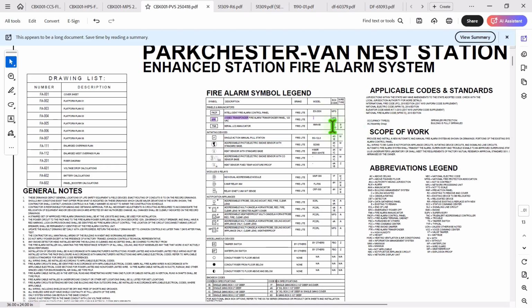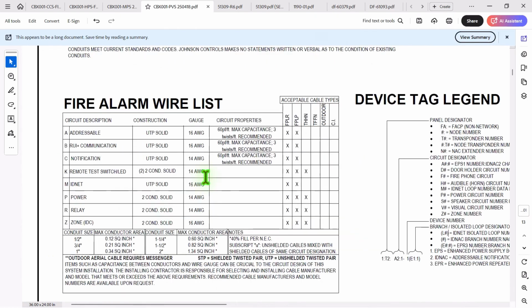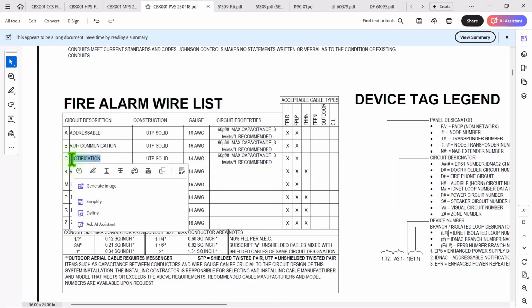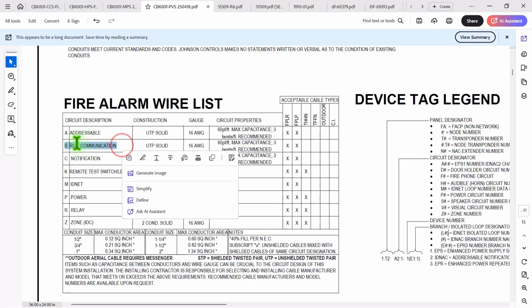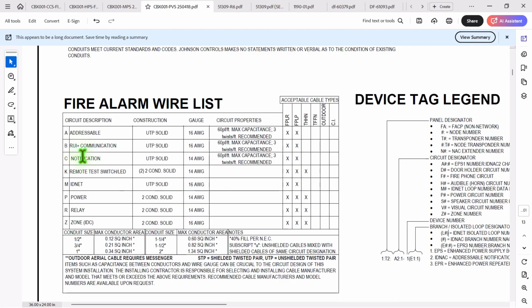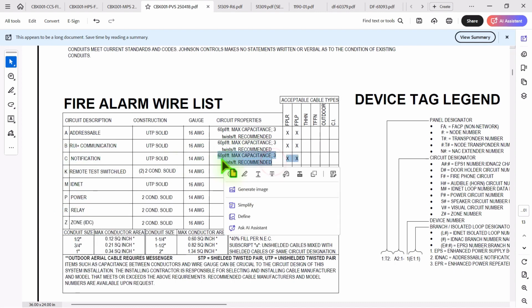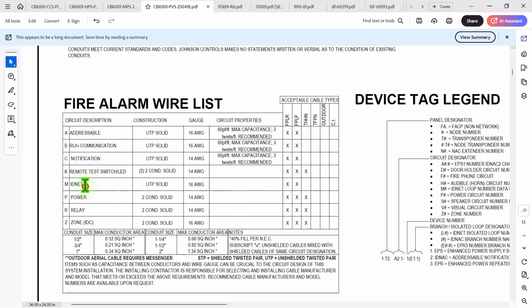Now for the wiring, you see B and P referring to this. This right here is for all the outputs, the NACs, the horns and strobes. This is going to be the communication for the remote annunciator. The remote annunciator could take this wire too, but we'll just name it power and put the same information down here for power. We don't need ID net, like K and these two right here. Let me highlight that.